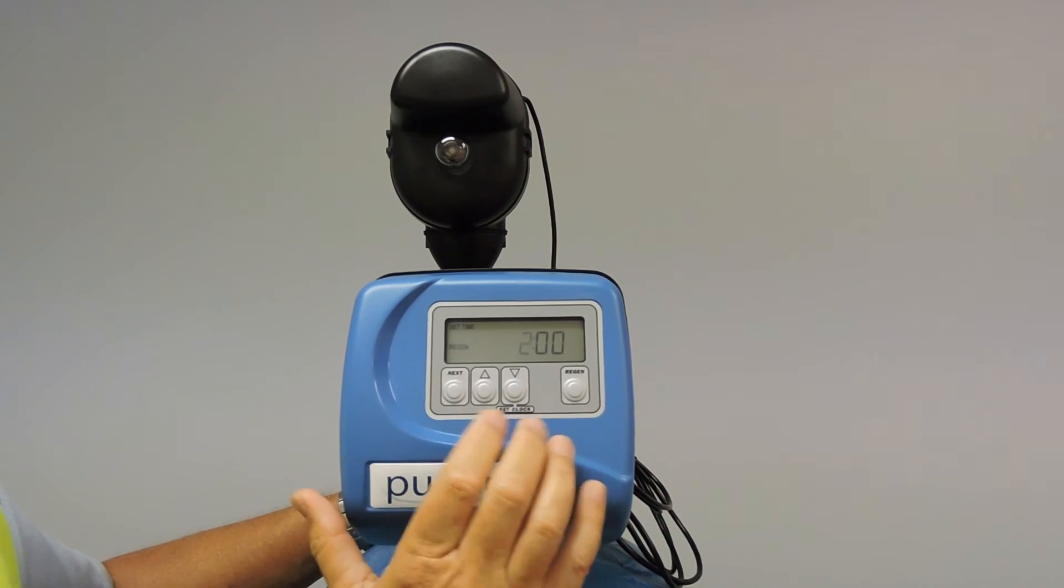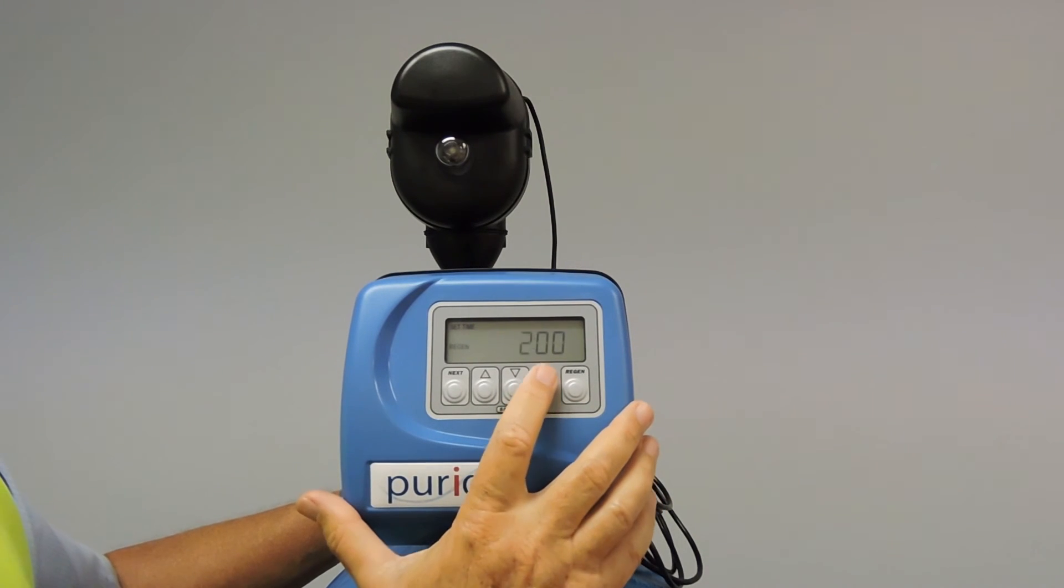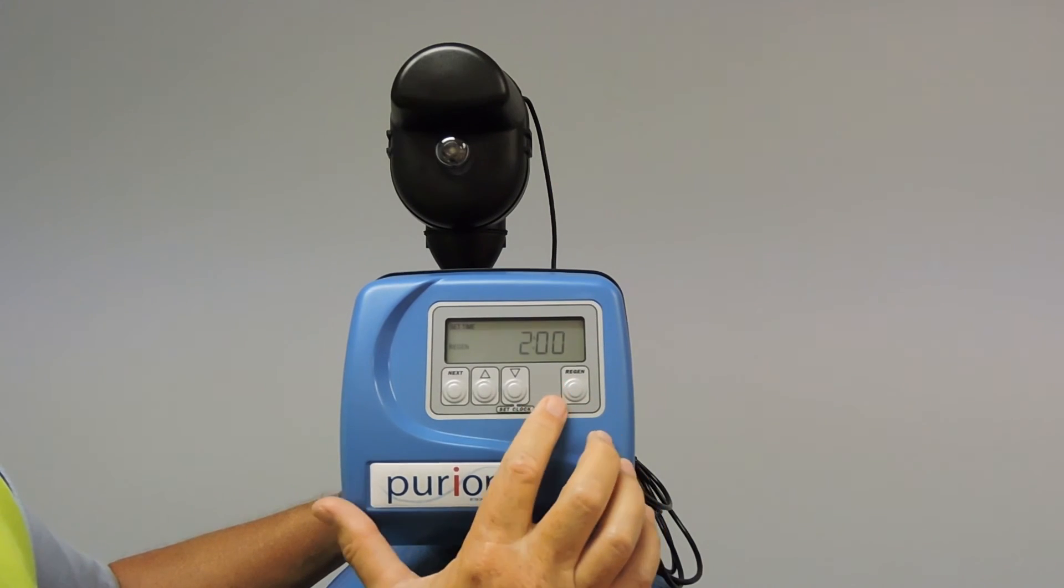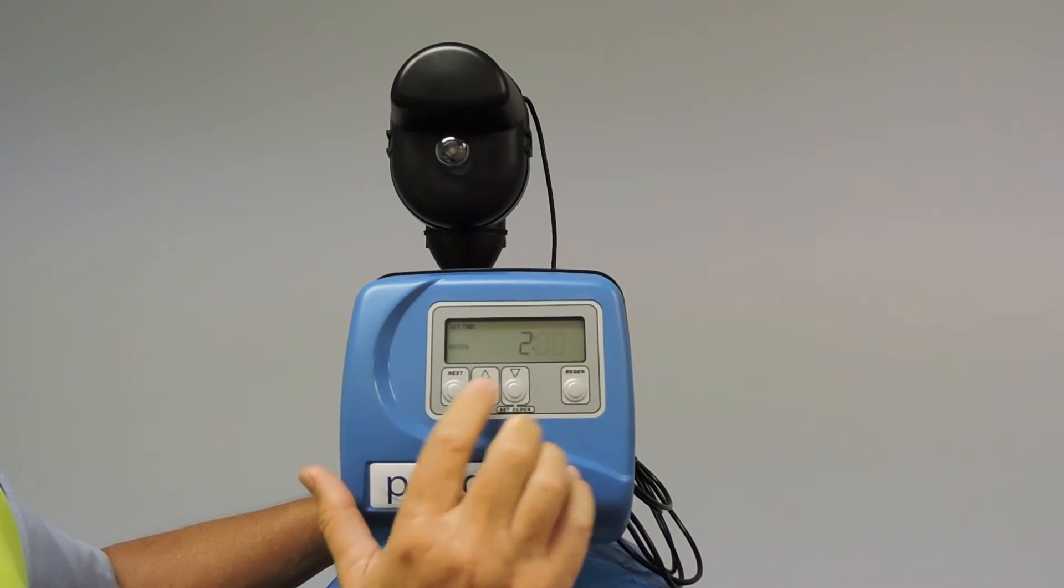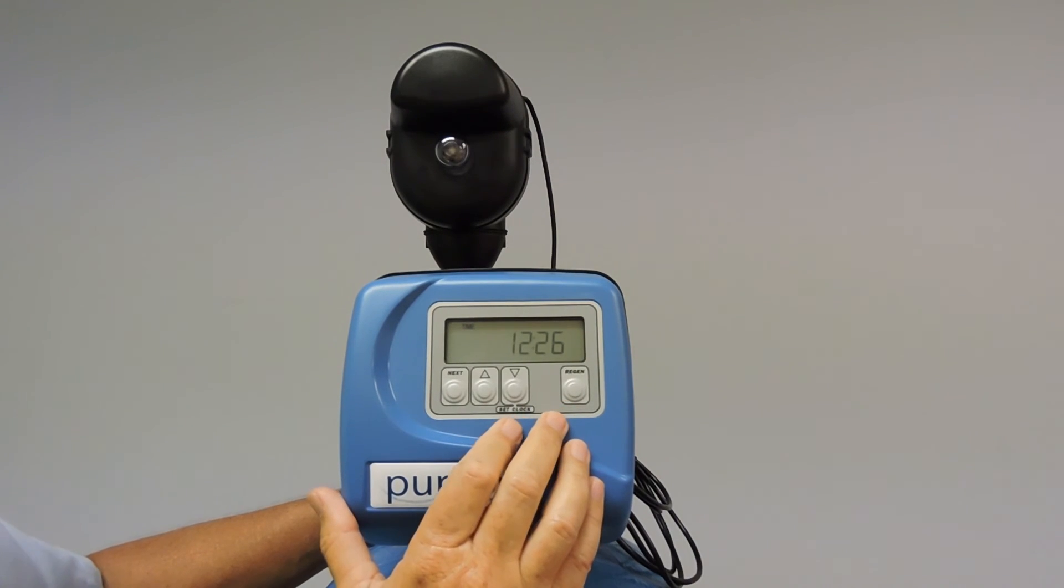And then this is your regen time. It is 2 o'clock in the morning, which is a convenient time because theoretically no water is being used. So we will accept 2 o'clock. If you need to change it, you simply just change the time of day. So next sets your hours. Then the minutes will be flashing. And we will accept that again. Then you're back to time of day.